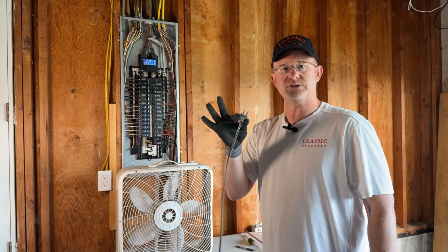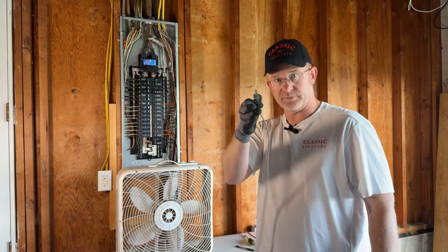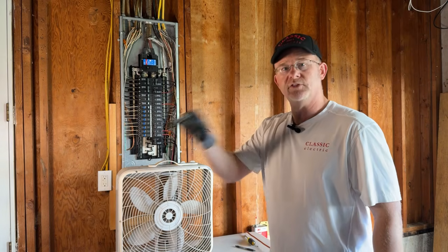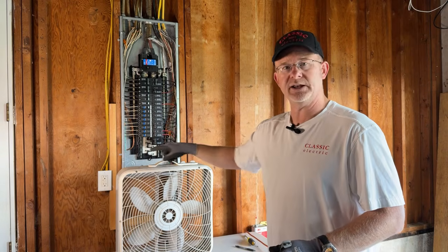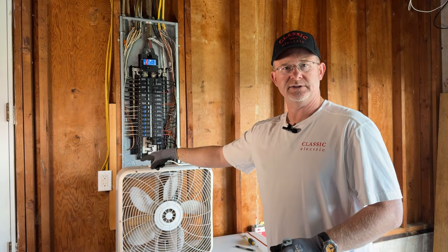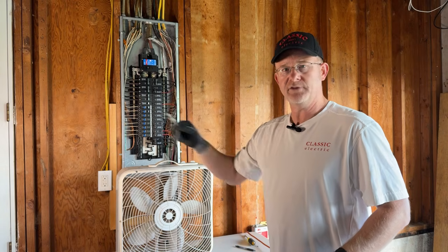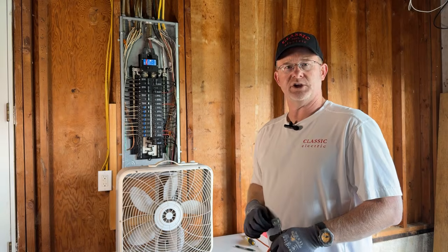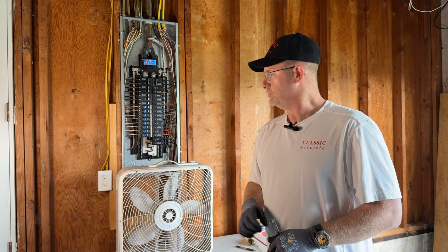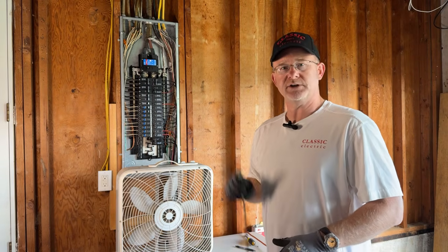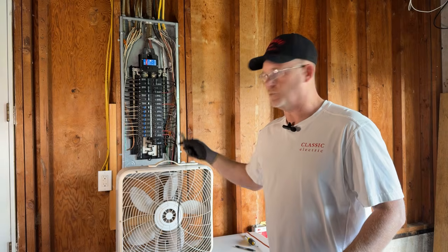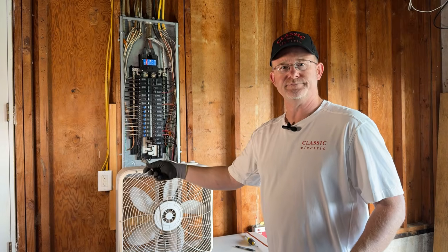Well, if you still have a piece of equipment, a Christmas light, a water feature, whatever it is, plugged in over there, you keep resetting it here and it just keeps popping and popping and popping. You've got to go around to everything out there, unplug it, reset the GFI. Well, that's cool. It reset. And then if you go out and plug something in, you don't need an electrician. Whatever you're plugging in is the issue.